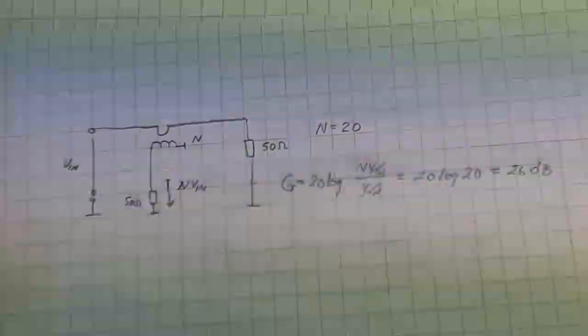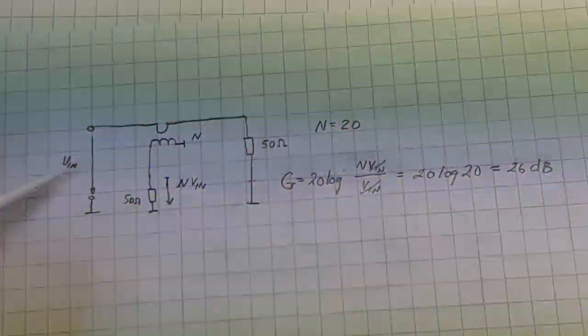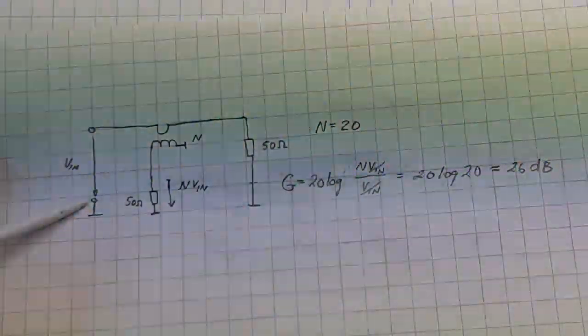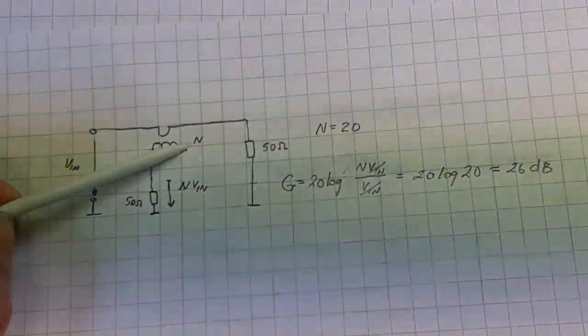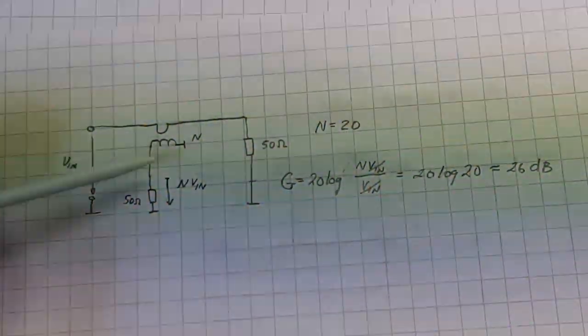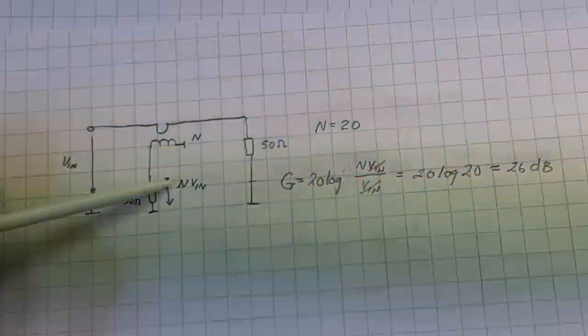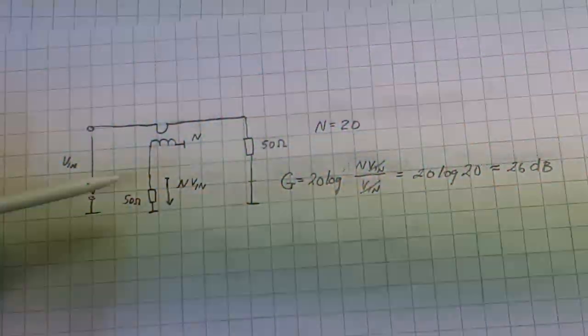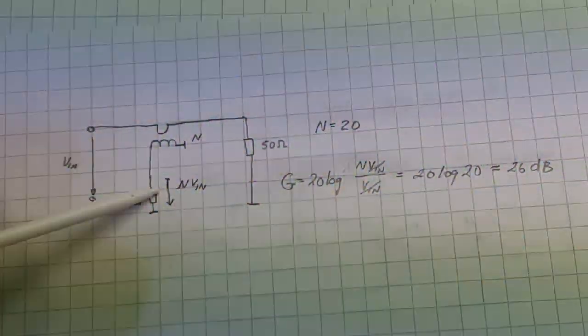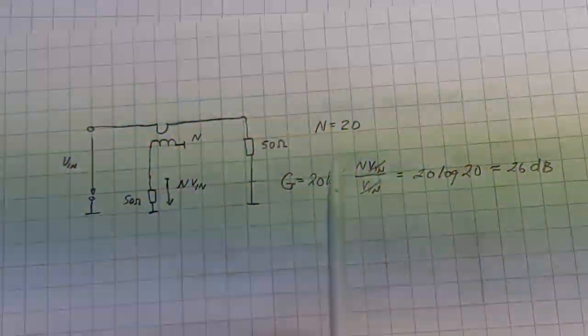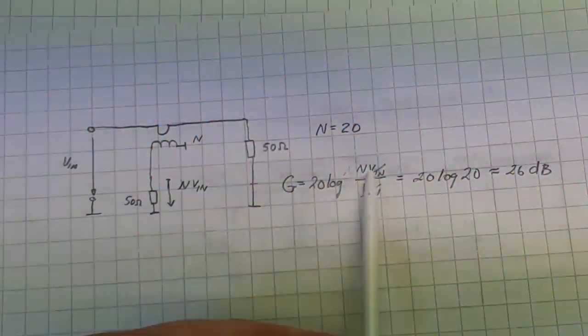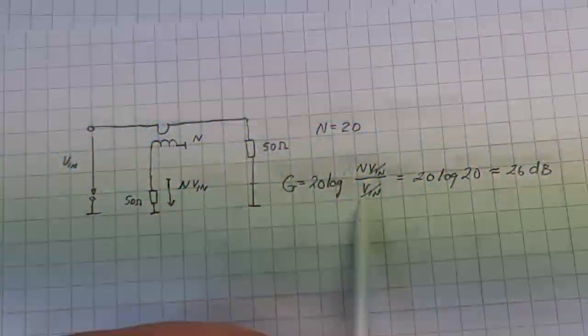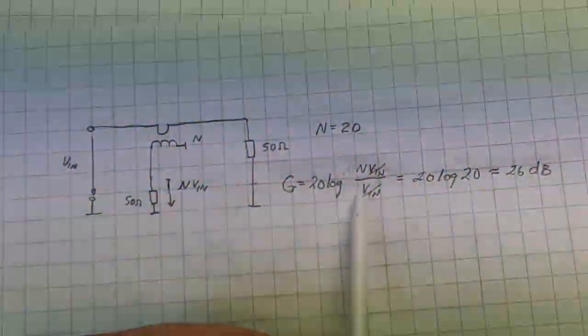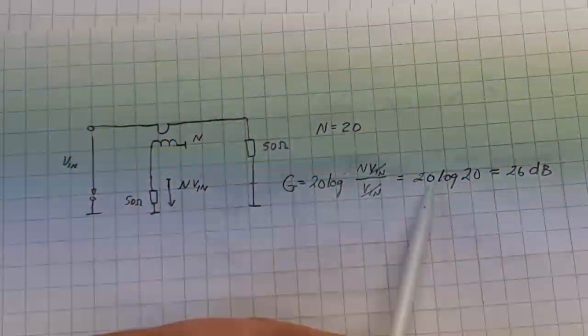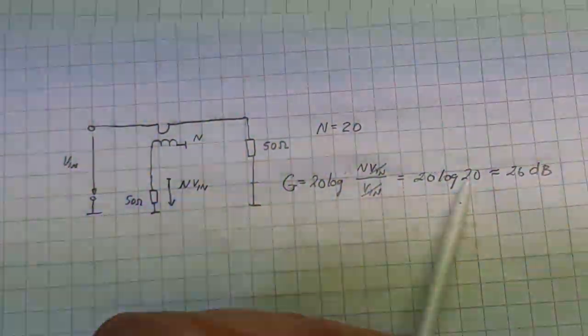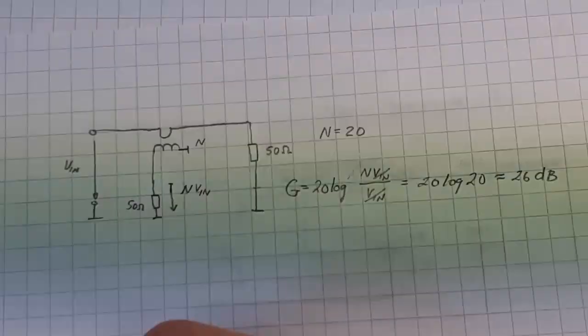What we expect to see is the following. If we have V in as the input voltage from the generator and a turns ratio of N in the first transformer, then the voltage at the transformer secondary would be N times V in. And if we calculate the ratio between these two voltages and express it in dB, then it would be the secondary voltage, which is N times V in divided by V in, and taking the logarithm of that fraction, we find out that it will be 20 times the logarithm of the turns ratio, which will be approximately 26 dB in this case.